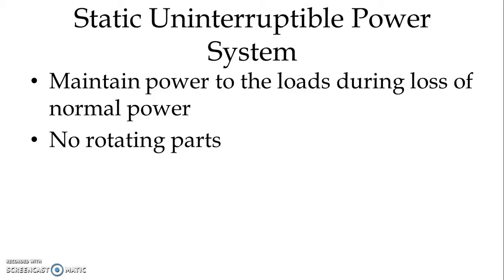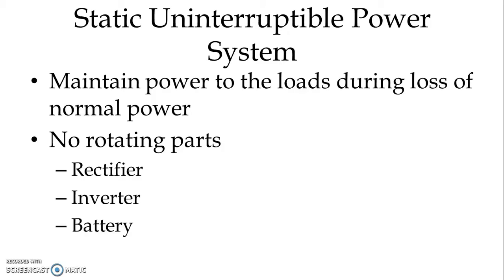In case of static uninterruptible power system, we have no rotating parts but major components, that is a rectifier. Rectifier we use to convert AC power into DC power and to charge our batteries. Then we have inverter. Inverter we use to convert available DC power in the battery to the AC power to feed the loads. And then we have battery. Battery we use to store the DC power, and we can use that stored DC power through the inverter when we have loss of normal power.